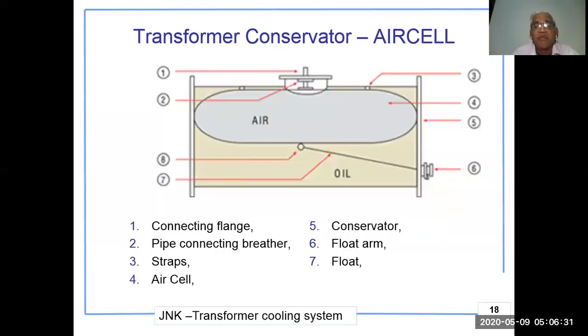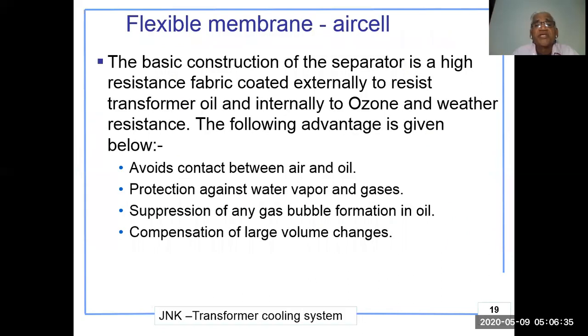The flexible membrane or air cell has a basic construction of high-resistance fabric coated externally to resist transformer oil and internally to resist ozone. Advantages include: avoiding contact between air and oil, protection against water vapor and gases, suppression of gas bubble formation in the oil, and compensation for large volume changes. Using the air cell, oil filtration is not required for up to five years, making it essentially maintenance-free, while ensuring the oil and internal paper insulation remain in good condition.